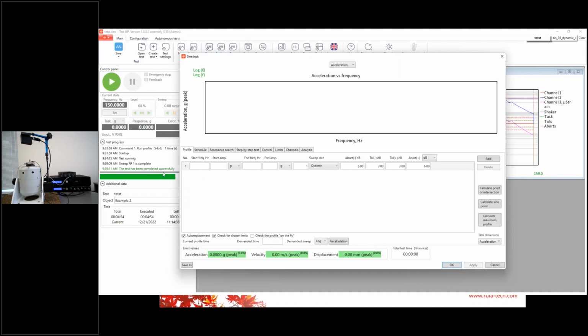For this test, we will run from 5 Hz, and let's set our start amplitude to 2 millimeters. Our end amplitude is 0.3 meters per second. Let's calculate the end frequency. Here you see the value. Let's add another line. We will run this test up to 5G.